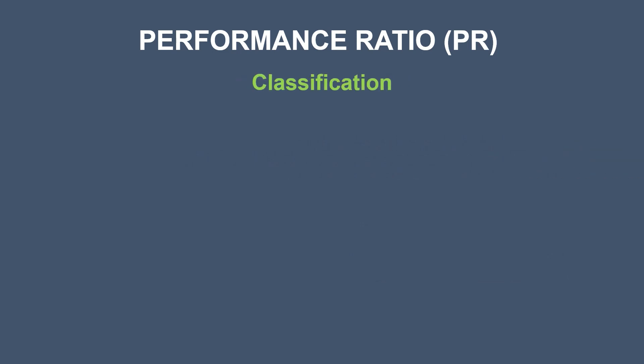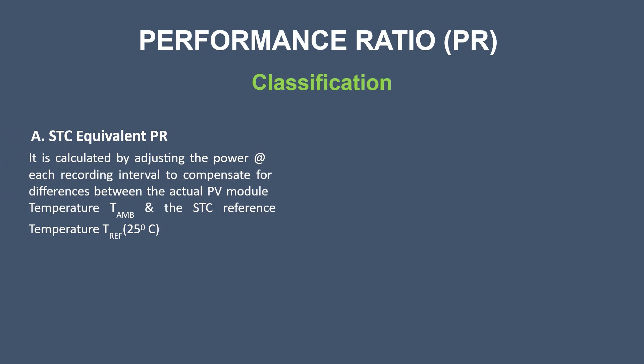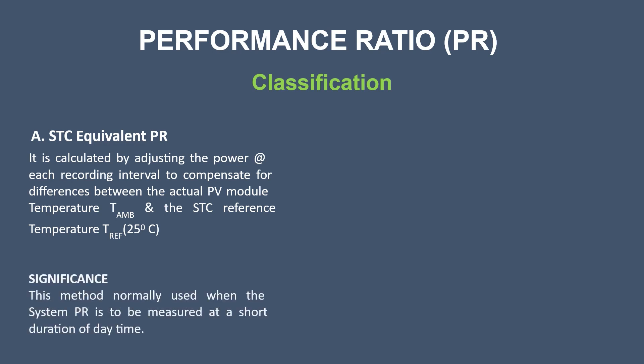Now let's look at the types of PR, each with their own significance and applicability. First is STC equivalent PR. It is determined by adjusting the power at each recording interval to compensate for the difference between the actual PV module temperature and the STC reference temperature. This method is normally used when the system performance ratio is to be measured over a short duration of daytime.